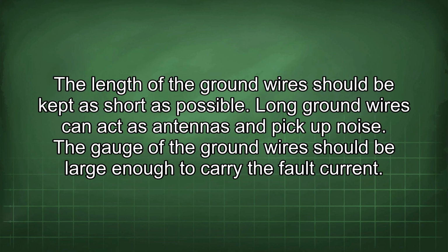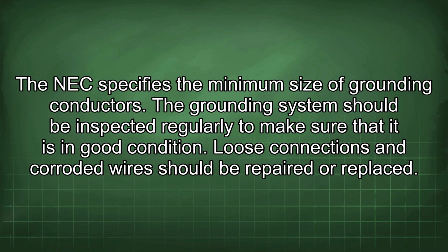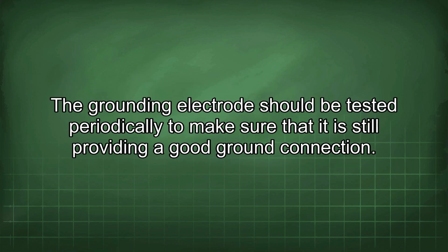The length of the ground wires should be kept as short as possible. Long ground wires can act as antennas and pick up noise. The gauge of the ground wires should be large enough to carry the fault current. The NEC specifies the minimum size of grounding conductors. The grounding system should be inspected regularly to make sure that it is in good condition. Loose connections and corroded wires should be repaired or replaced. The grounding electrode should be tested periodically to make sure that it is still providing a good ground connection.